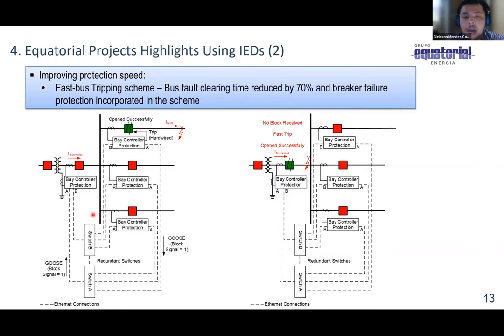Another project that we have is the fast bus trip scheme, where using the communication among the relays, we can reduce the time of the bus fault clearing. So if I identify a fault in front of a feeder relay, it sends a signal to the main relay and says to the main relay, I'm tripping, so you don't have to trip.